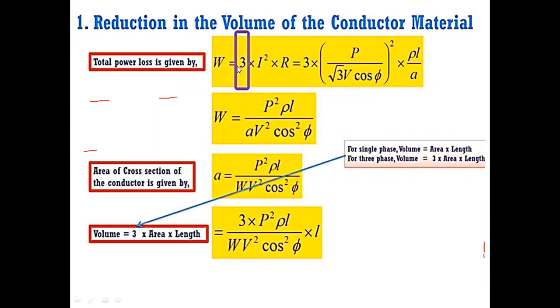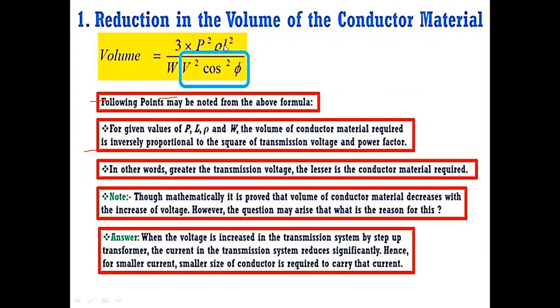The total power losses in the three-phase system will be equal to 3 times I square R. So replacing the value of I from the previous slide and R as well, we'll get P square rho l over A V square cos square phi. Because we are interested in volume, we must have the area. Area is equal to P square rho l over W, the power loss, V square, which is the voltage, cos square phi. Now the volume for a single conductor is area into length. For the three phase, the volume would be 3 times area times the length. So l will be multiplied with this l, and we will have l square, 3 into P square rho l square over this.